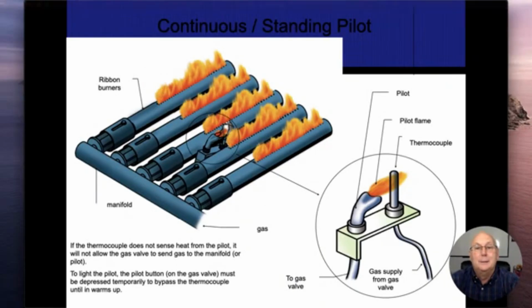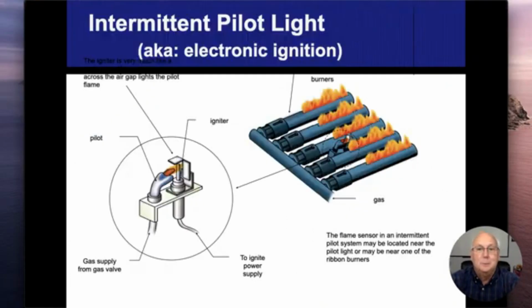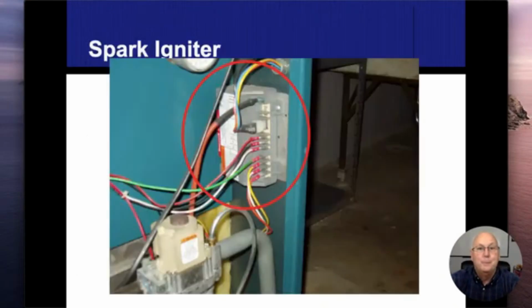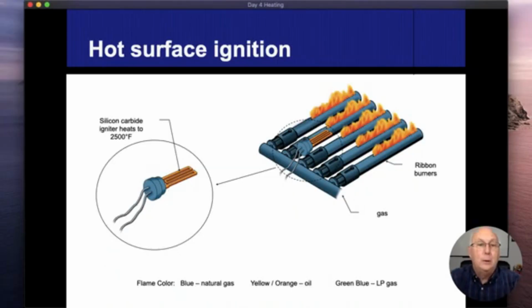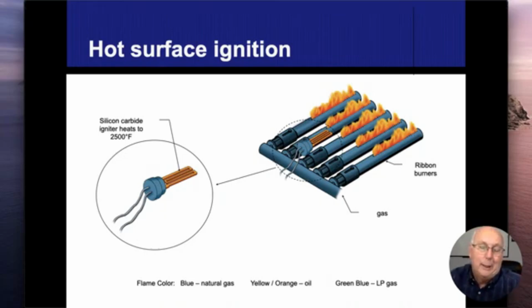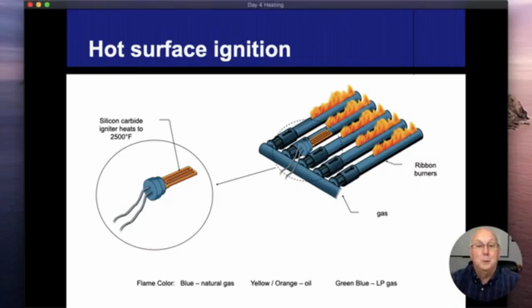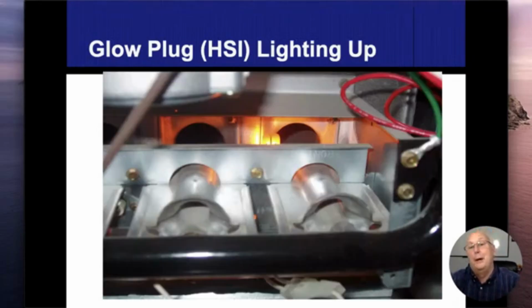Pilot lights coming on there. Sometimes we see silicon igniters. Sometimes we see pilot lights. Sometimes spark igniters. Different things that we're going to use to start the fire. When you hear the clicking coming out of a furnace, that's the spark igniter. This big gray box is actually what creates that and verifies that it's running. Nowadays, everything kind of goes with what I call glow plugs. The proper term is a silicon igniter or heat igniter, hot surface ignition. All those are acceptable. When this thing starts up, it's going to glow bright orange.